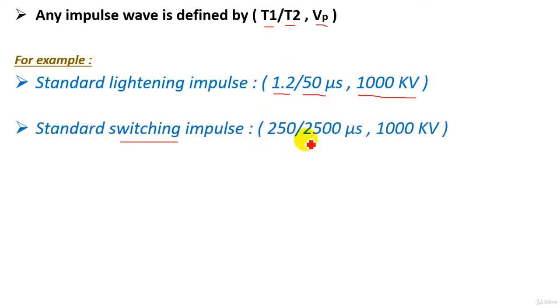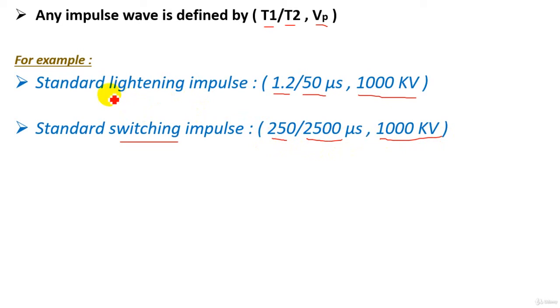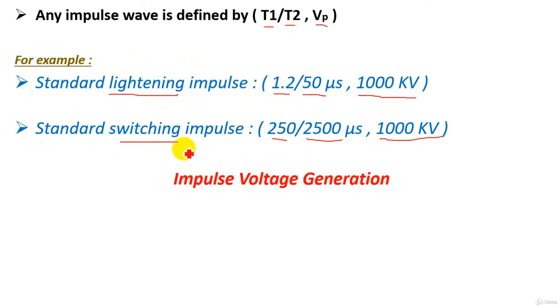For the standard switching impulse, the waveform is 250/2500 microseconds and 1000 kilovolts — meaning a rise time of 250 microseconds, a tail time of 2500 microseconds, and a peak voltage of 1000 kilovolts. So we have two standard impulse waveforms that can be produced in the lab: the standard lightning impulse and the standard switching impulse.